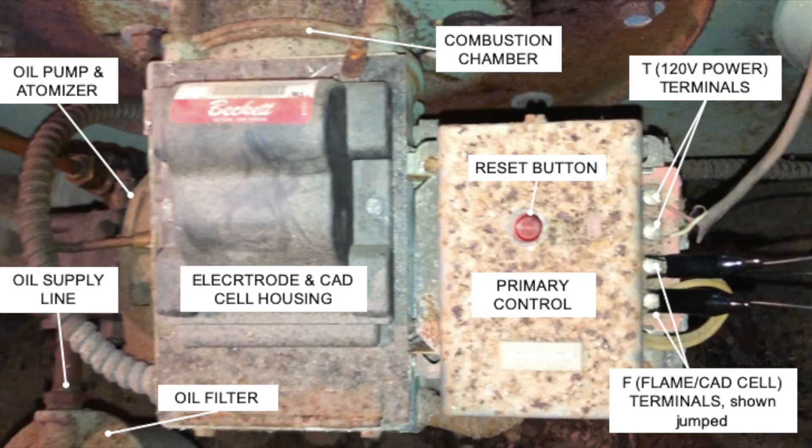The F terminals, which are shown jumped out, provide feedback from the flame sensor or CAD cell within the housing back through the primary control. That yellow wire on the right side of the picture goes underneath the primary control and feeds back into it.